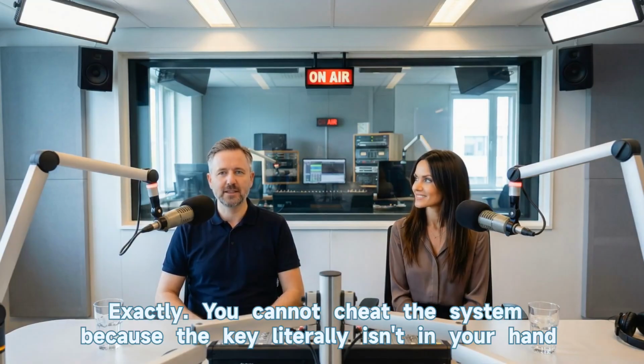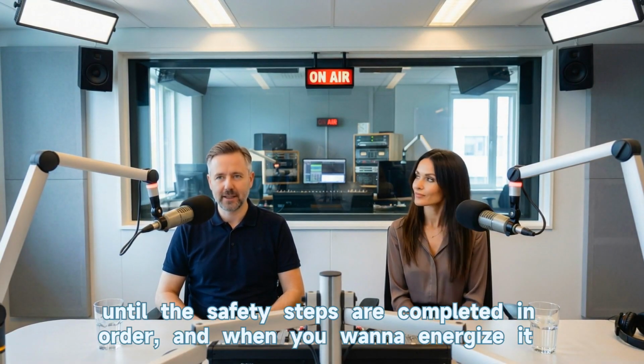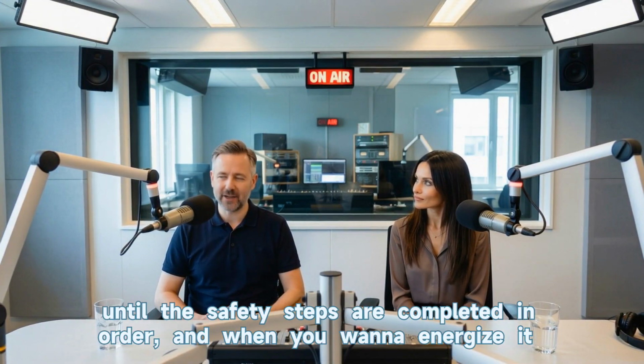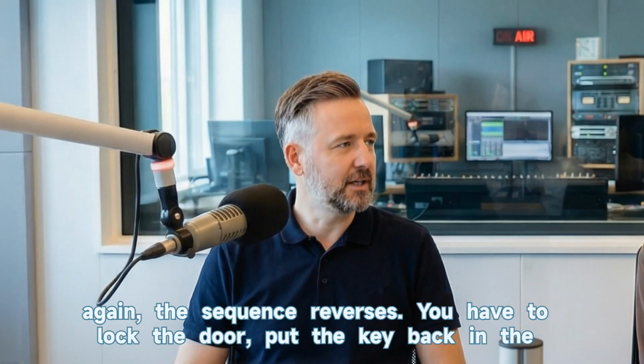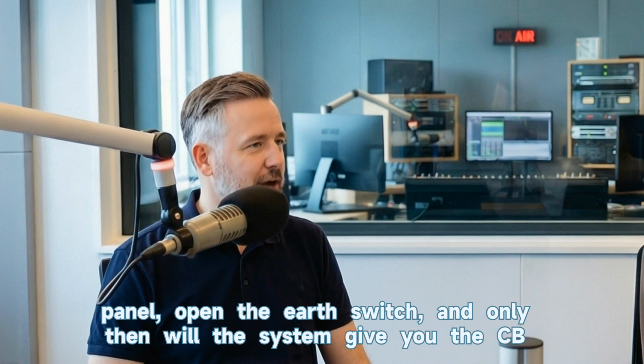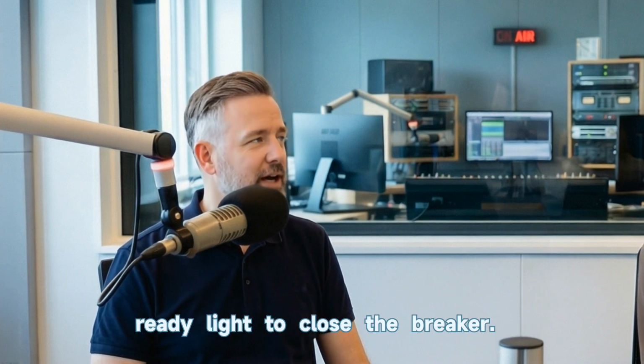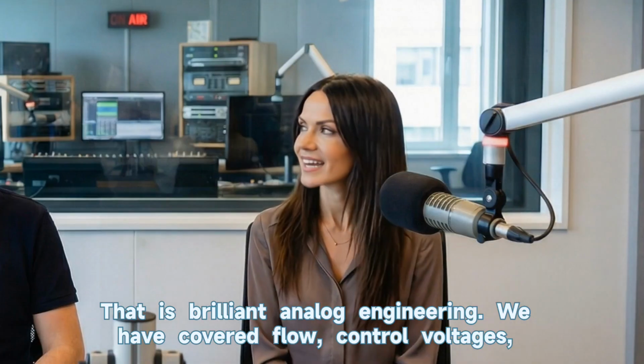You cannot cheat the system because the key literally isn't in your hand until the safety steps are completed in order. And when you want to energize it again, the sequence reverses. You have to lock the door, put the key back in the panel, open the earth switch, and only then will the system give you the CB-ready light to close the breaker. That is brilliant analog engineering.